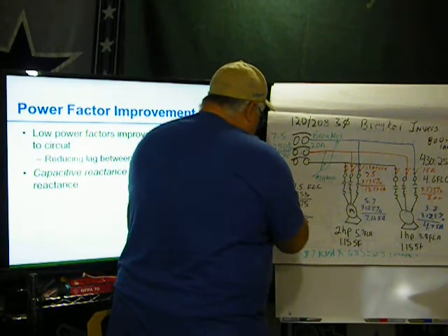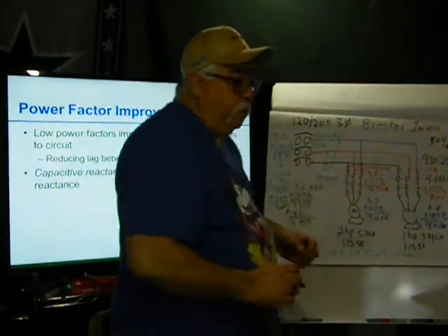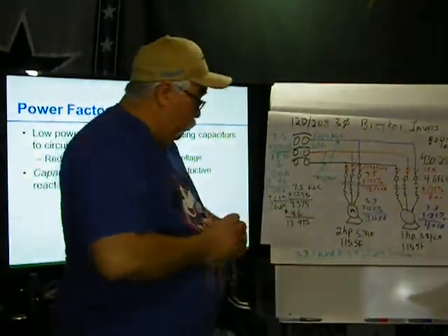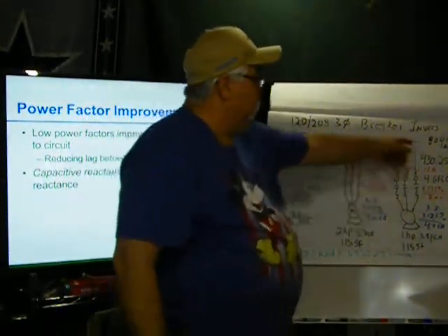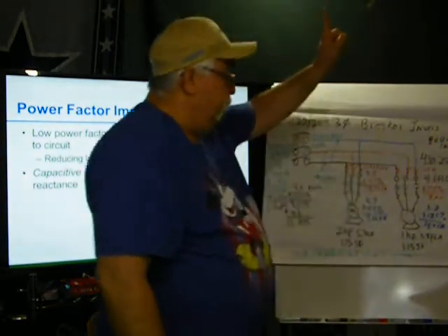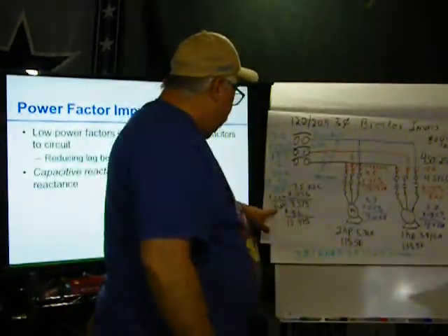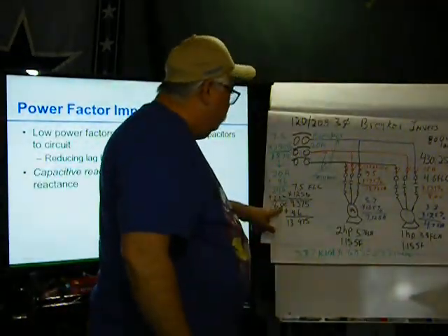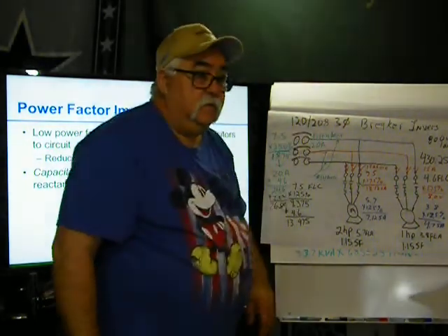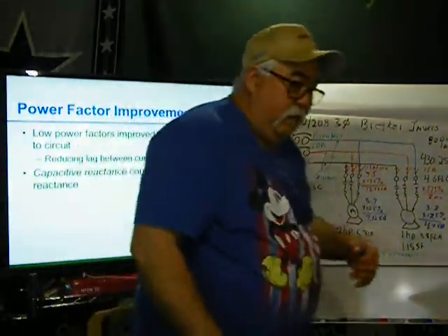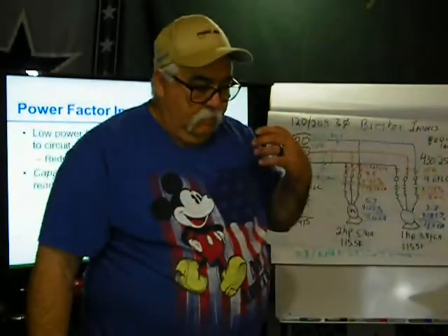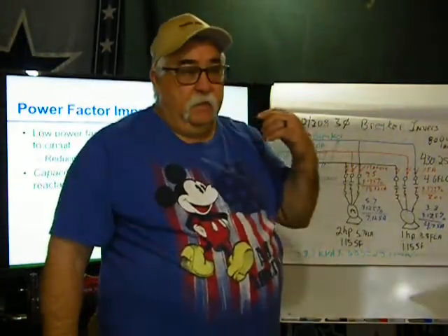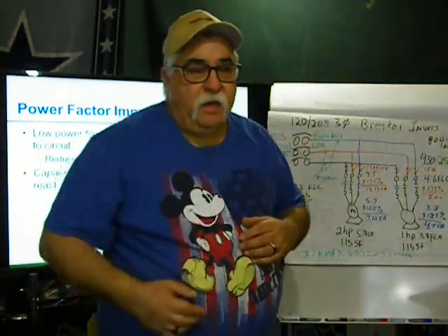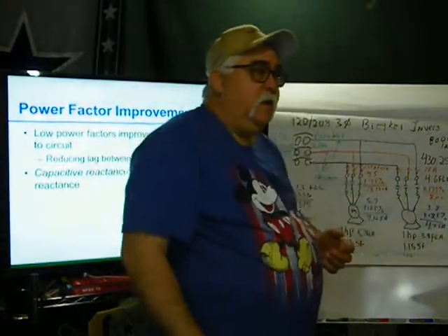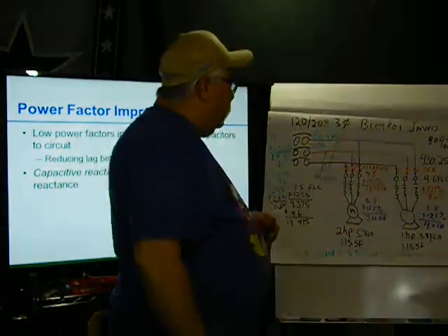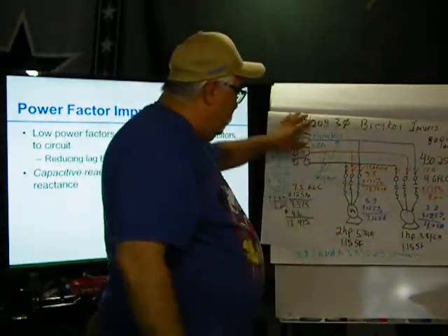So this would be 26.8. Now I got a 25 amp breaker, because this 800 watt load took it above 25. I'm at 26.82. So that's adding other loads. In the answers, I forgot, I just got the 480 volts. I made it where I could do it simple in my head, just so you got the idea. Again, it's just trying to get everything.